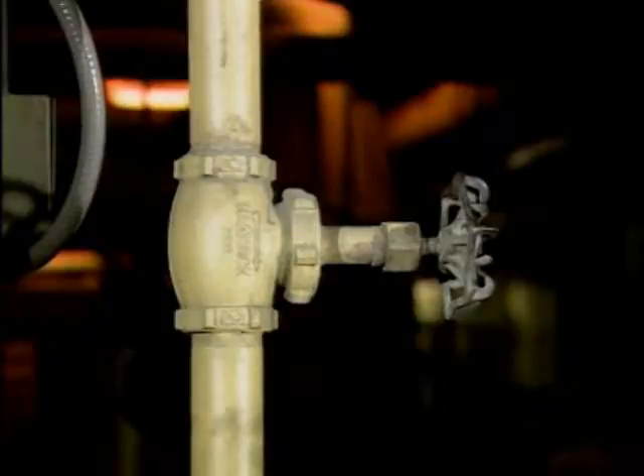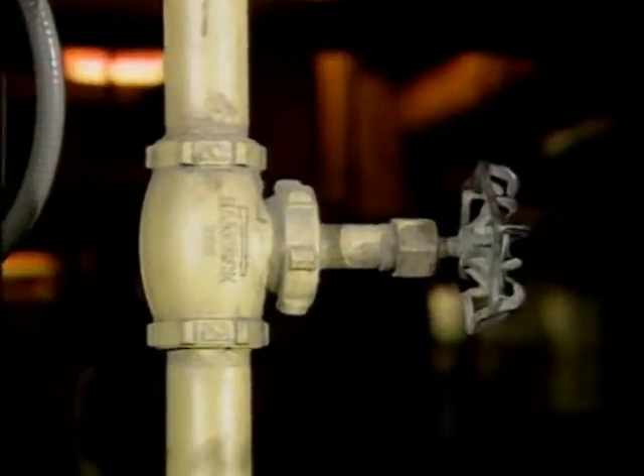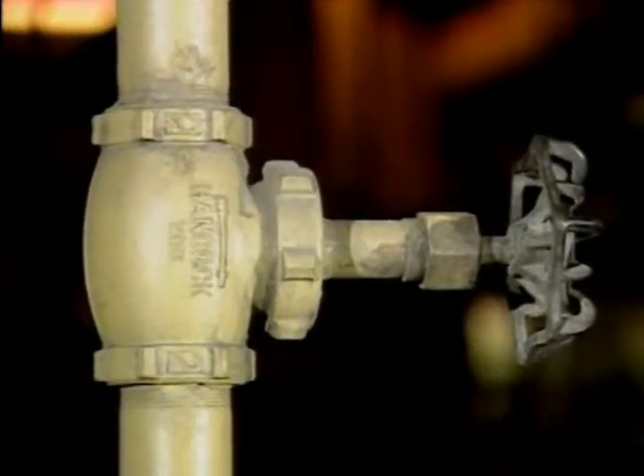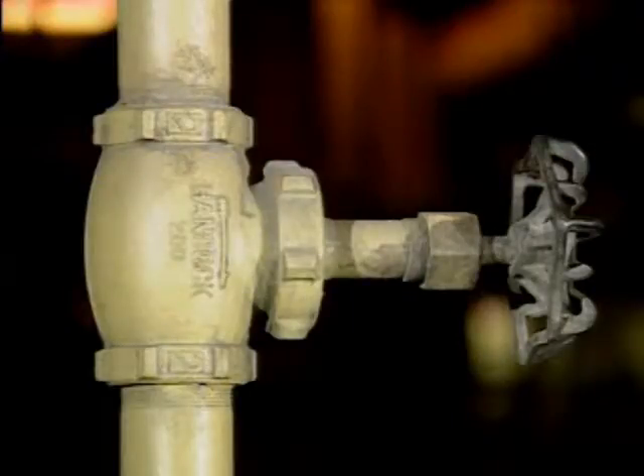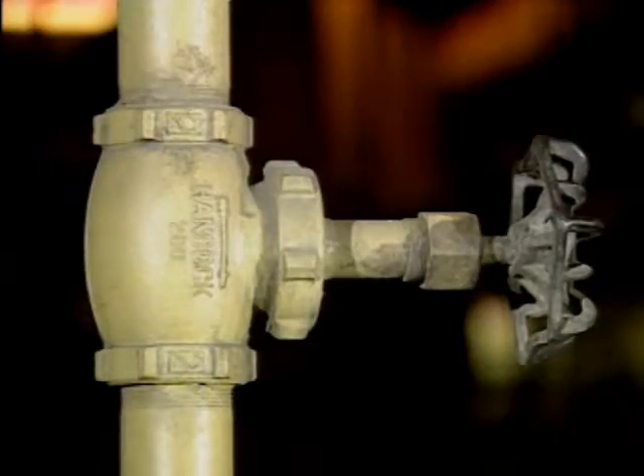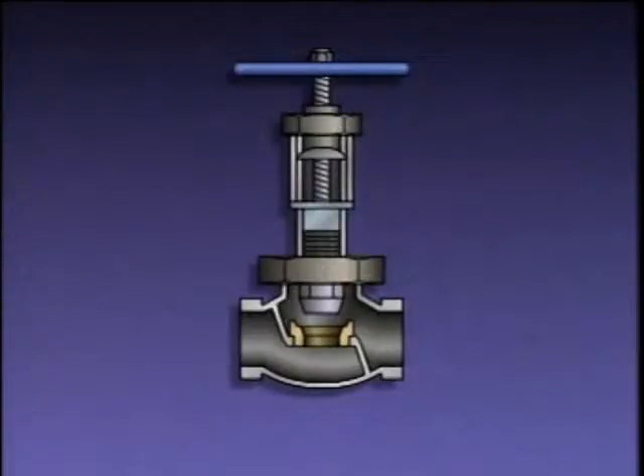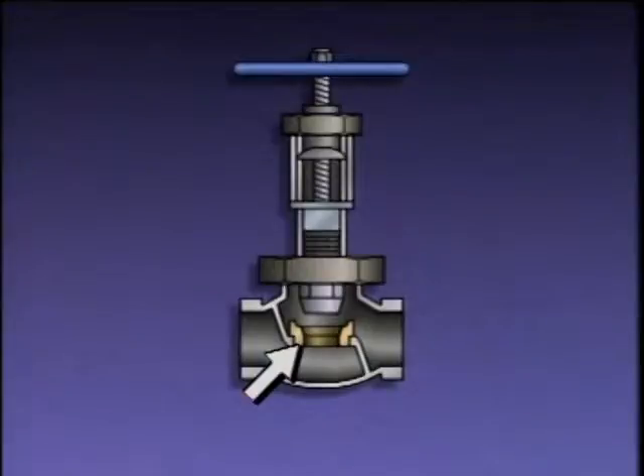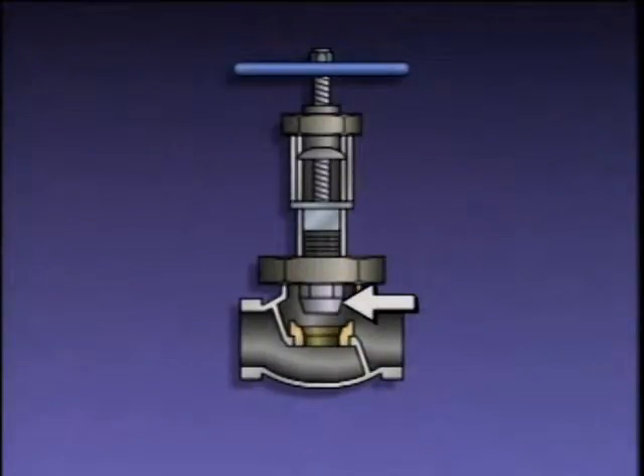Another type of valve commonly used in process systems is the globe valve. A globe valve can be used as an on-off valve to isolate components and as a throttling valve to regulate fluid flow. A globe valve consists of a globe-shaped valve body, a seating area or seat, a bonnet, a disc, and a stem with a handwheel attached to it.